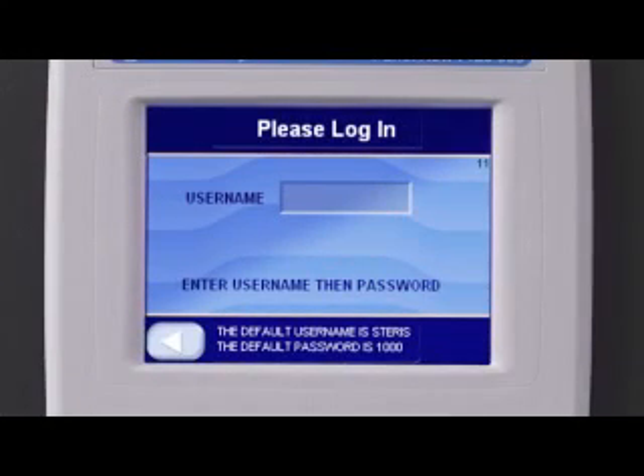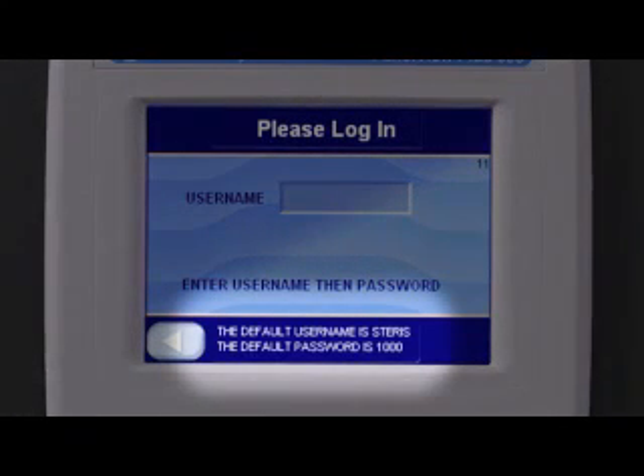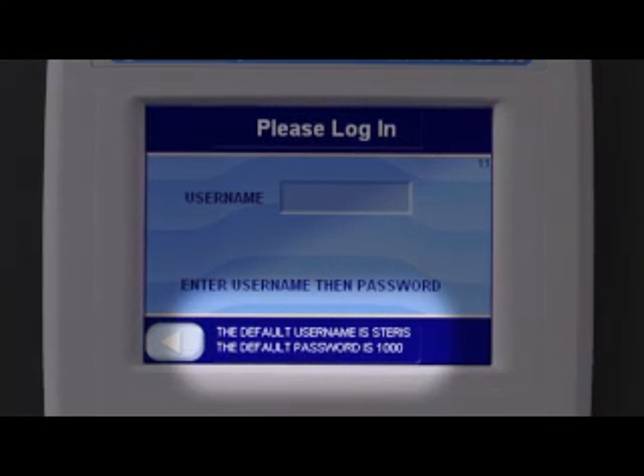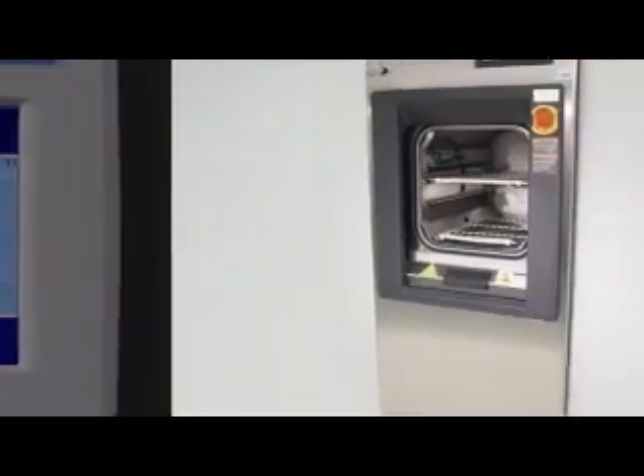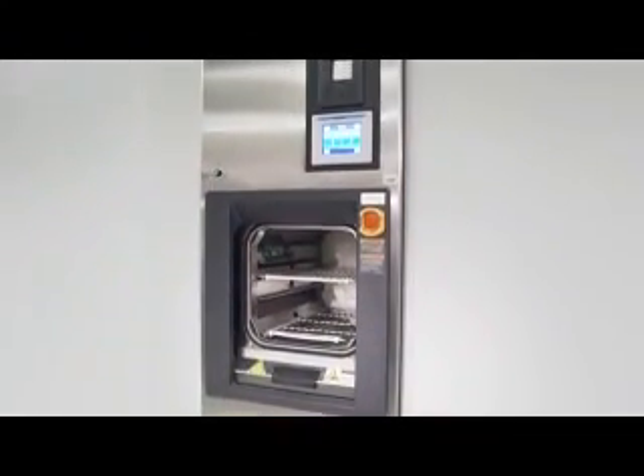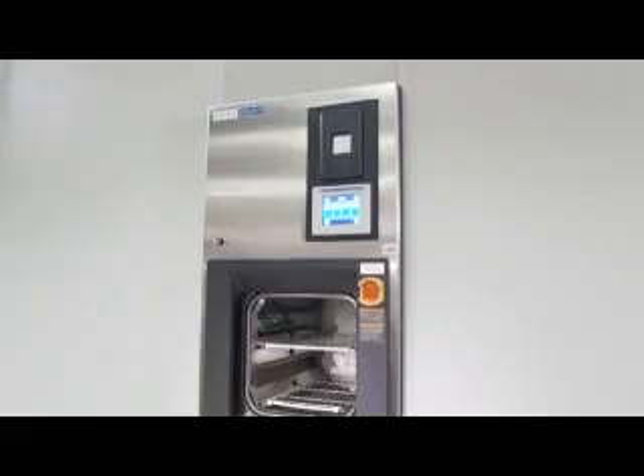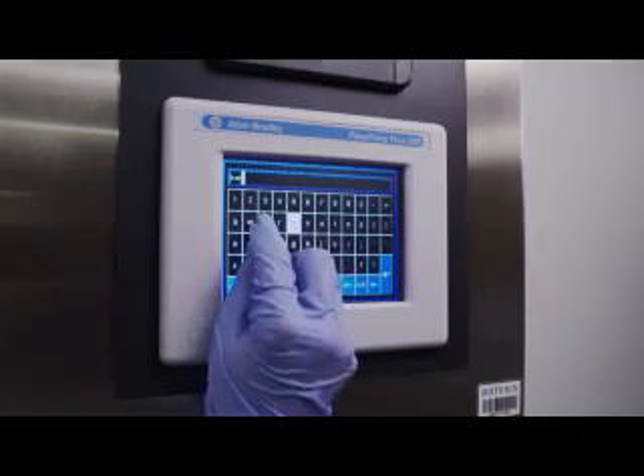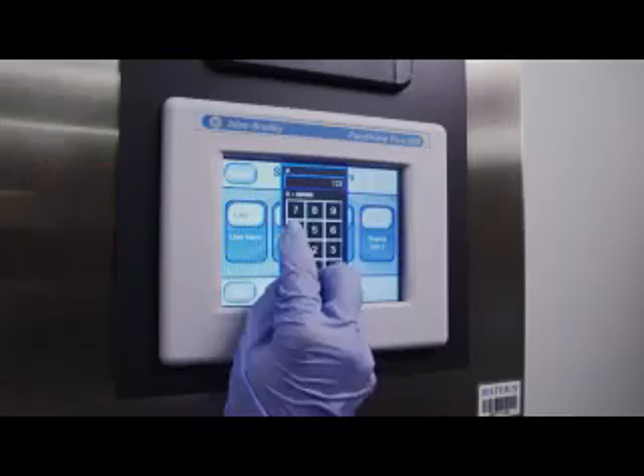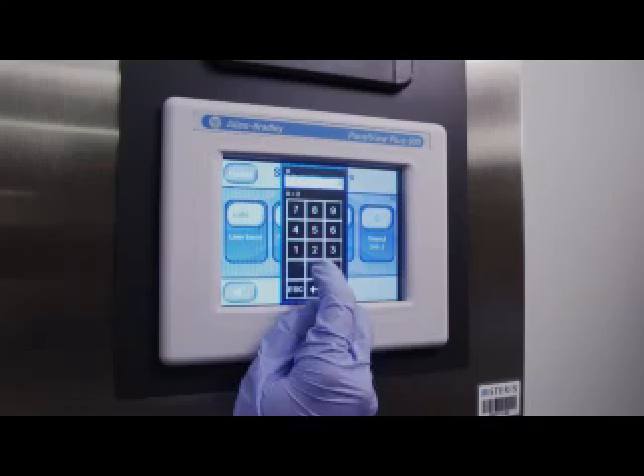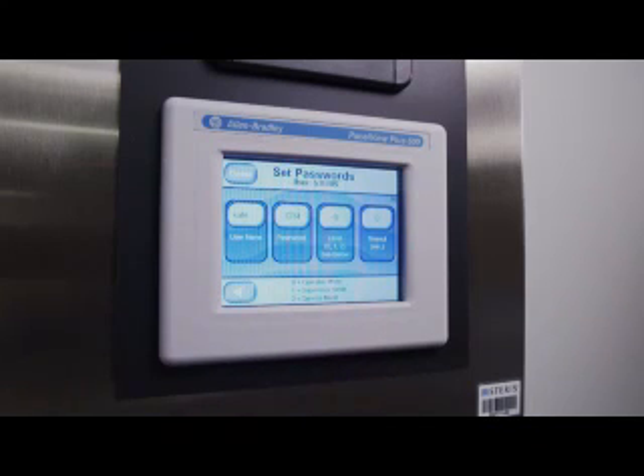One note regarding login names and passwords. The default login of STERIS and password of 1000 will remain visible on the login screen until the supervisor login name is changed. With the AMSCO Lab Series sterilizer, up to 12 users can be assigned. Simply assign a username, set the password and required access level. There is also a setting for the amount of time allowed to elapse before the unit returns to standby mode, and the password needs to be reset.